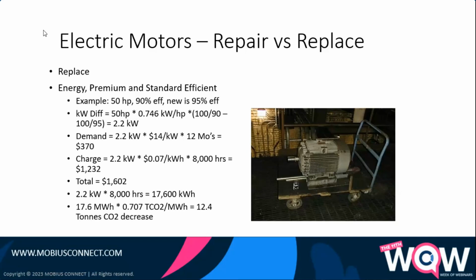If I have $14 per kilowatt demand, I multiply that by 2.2 times the 12 months, and that's $370. So demand is usually the maximum kilowatts you draw in a 15-minute period, which is pretty standard with utilities. The charge related to that would be 2.2 kilowatts times, in this case, 7 cents per kilowatt hour times 8,000 hours of operation, which is almost full time. There's 8,760 hours in a year. That would be $1,232. Total would be $1,600.